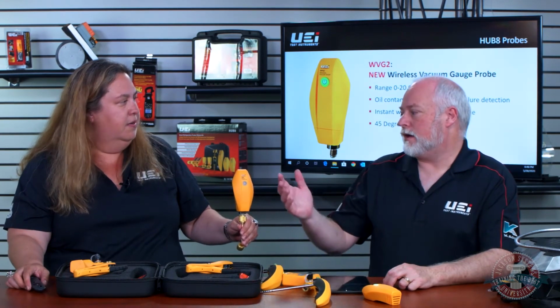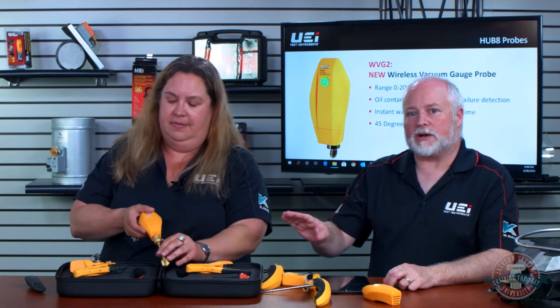Absolutely. Like we were talking earlier, how important a micron gauge is because of the fine measurement. Because really what we're doing when we're pulling a vacuum is we're lowering the boiling point, right? We all know at atmospheric pressure, what does water boil at? 212 degrees, right? If we can get down to around 500 microns, water will boil at about minus 15.